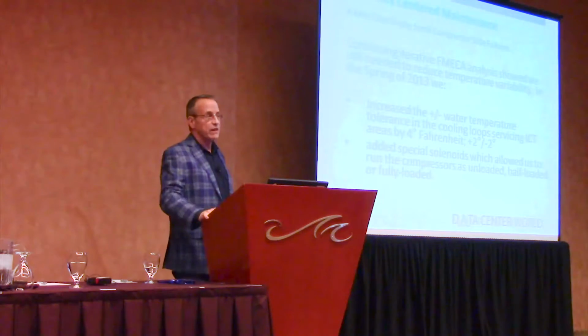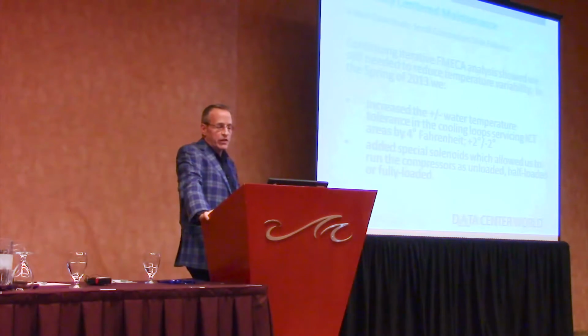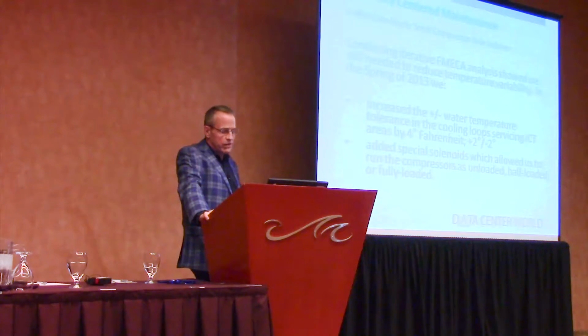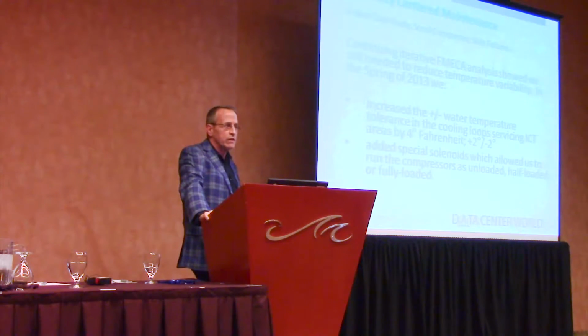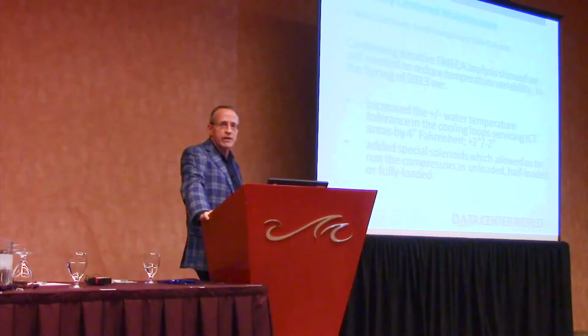We experienced the failures, started examining parameters again, and we decided that we didn't really have to quite so precisely control the water temperature going to the AHUs out on the computer room floor. So we pushed that plus or minus 2 degrees in each direction up and down.